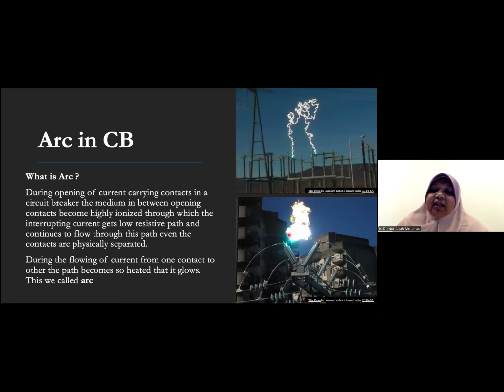So here, this is outdoor switching. When we open the circuit, there is arcing. So in a circuit breaker, the major use of the insulation material is to quench this arc. If you are at home, maybe you have experienced sparking when you open a switch. That we also consider as an arc, but it is a small arc. This is in high voltage operation. So in a circuit breaker, the insulating material must be able to stop this arcing. During operation, when the contacts open, the ionization of the medium produces arcing. Then the circuit breaker's insulation material needs to stop this arcing as soon as possible.